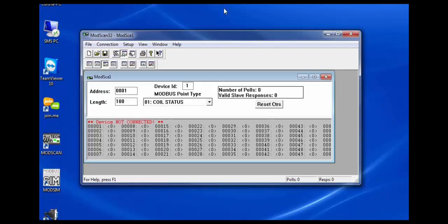And if you recall, Modbus masters, one of the things that they do a lot of is acquire data from Modbus slaves, right? To do so, they have to have an idea of the unit ID of the slave plus the register address or register addresses. Remember that. So how do we tell ModScan to act like a master in a certain way? Well, let me use an example. Remember our very first example where we were looking at the query response cycle, where we were acquiring the pressure at 30,019 from PLC with ID 22?